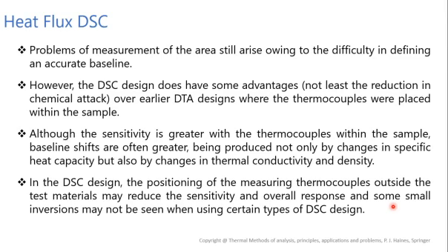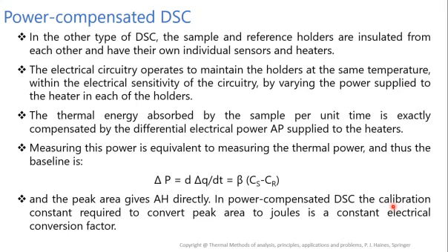In the DSC design, positioning the measuring thermocouples outside the test materials may reduce the sensitivity and overall response, and some small inversions may not be seen when using certain types of DSC design. So this is about the heat flux DSC.